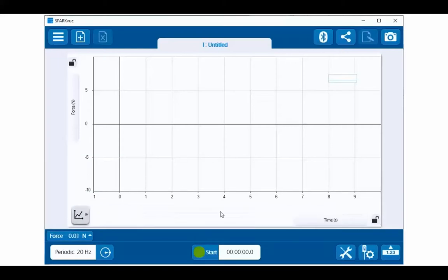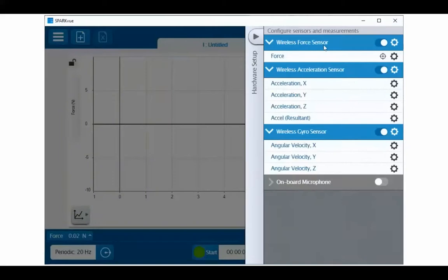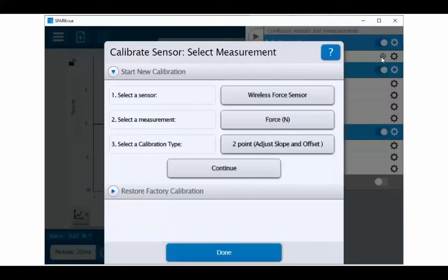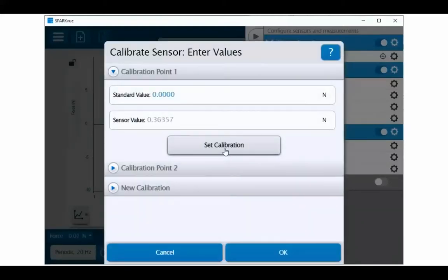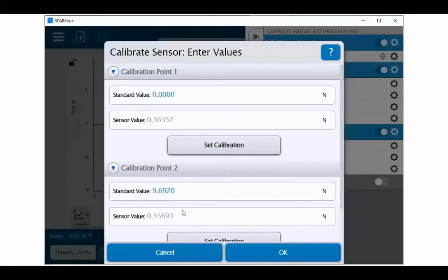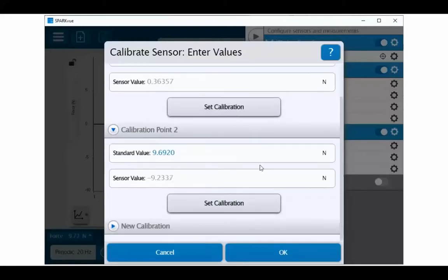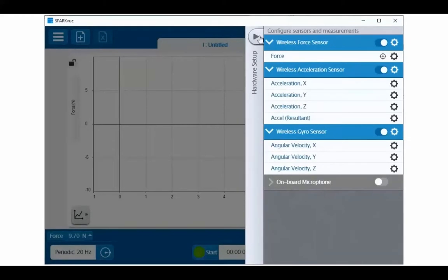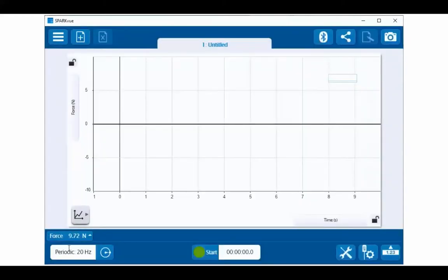Now we'll select on the Tools menu, and we'll select the calibration crosshairs. The 2-point slope offset has been selected. We'll click on Continue. Since we have the 0 to the force sensor right now, we'll click on Set Calibration. We'll open up Calibration Point 2. Now we'll gently hang our calibrated weight on there. The standard value is the force of gravity that we would expect on this standard. Then click on Set Calibration. Click on OK, and then close the side drawer. Now we see a live display of the data for our hanging mass.